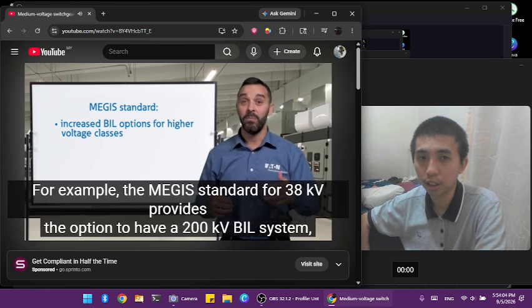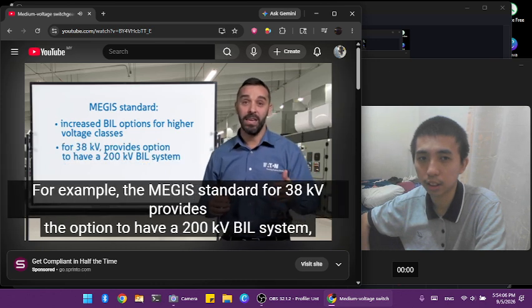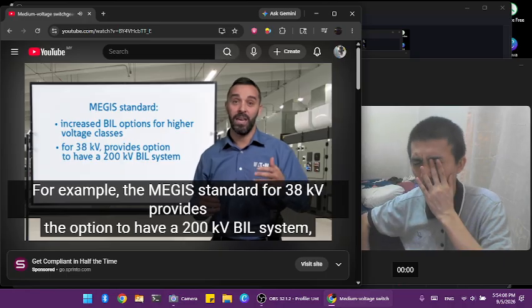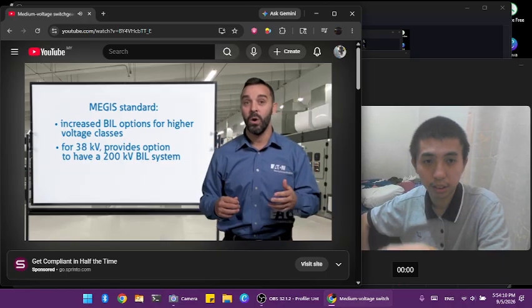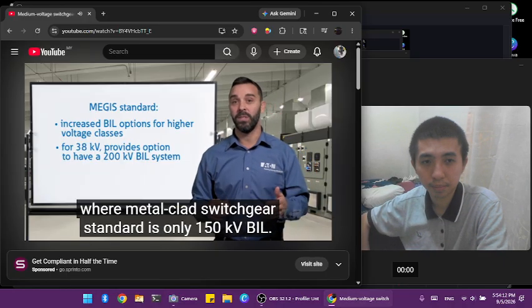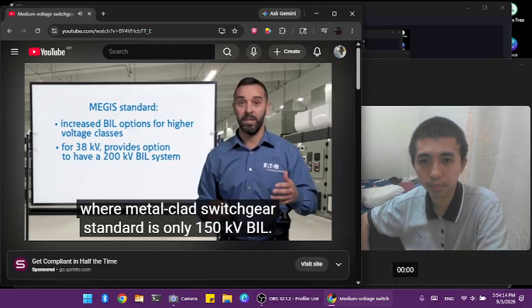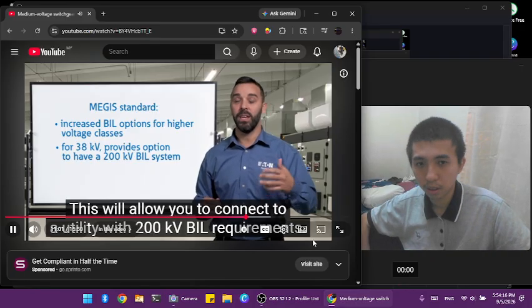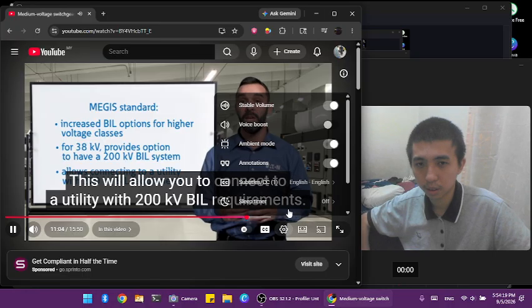For example, the MEGIS standard for 38 kV provides the option to have a 200 kV BIL system, where metal-clad switchgear standard is only 150 kV BIL. This will allow you to connect to a utility with 200 kV BIL requirements.